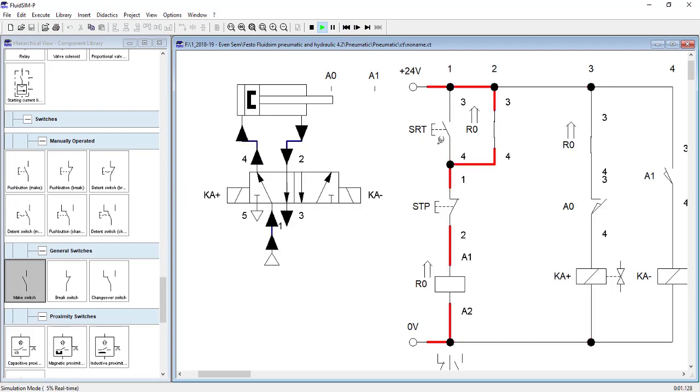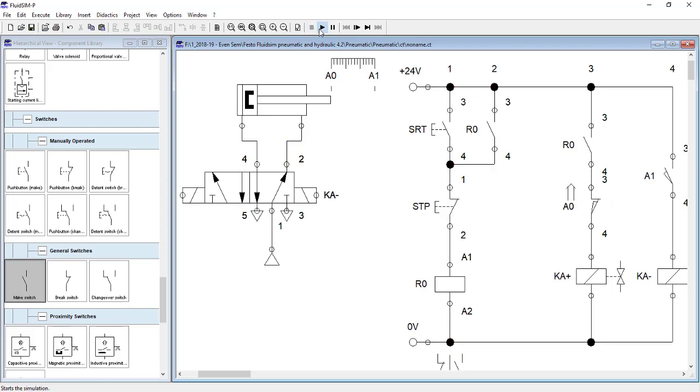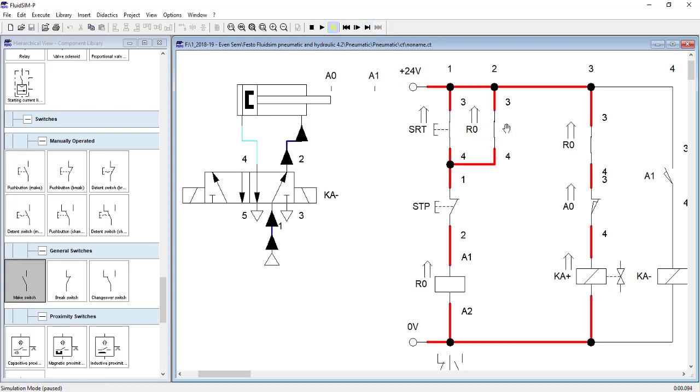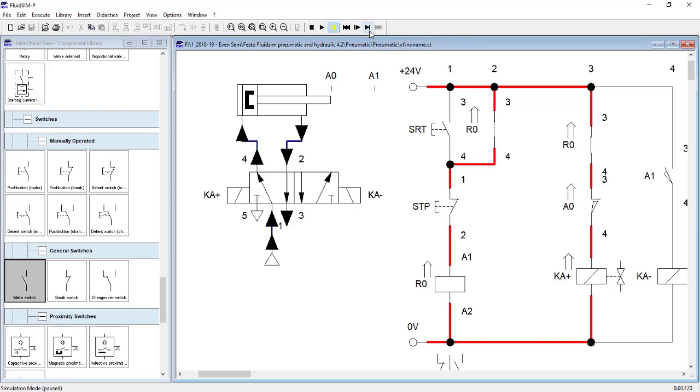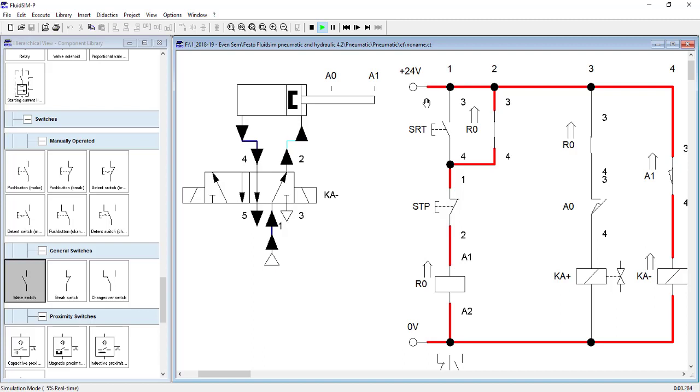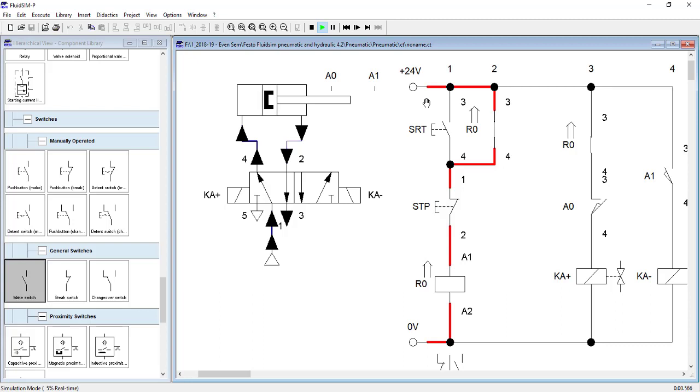When you press the start push button, electricity flows to relay 0. Because electricity flows to relay 0, the NO of relay 0, which is in parallel with the start push button, gets FC, functionally closed. Then even after the start push button is left, electricity keeps reaching relay 0 through the relay 0 NO. The system will work perfectly, no problem. It will continue operating continuously till I push the stop button.